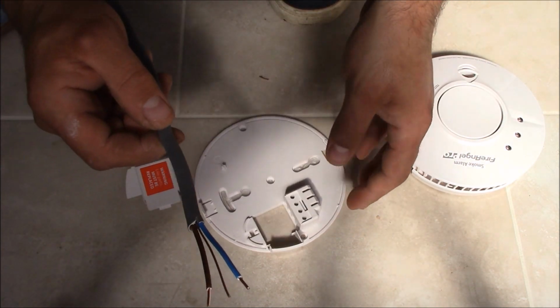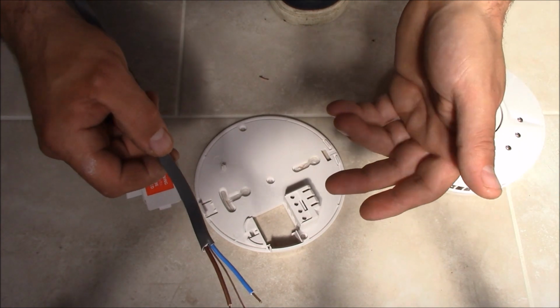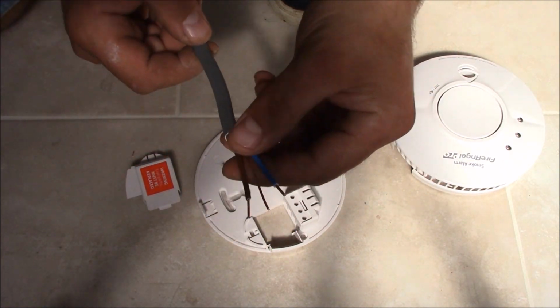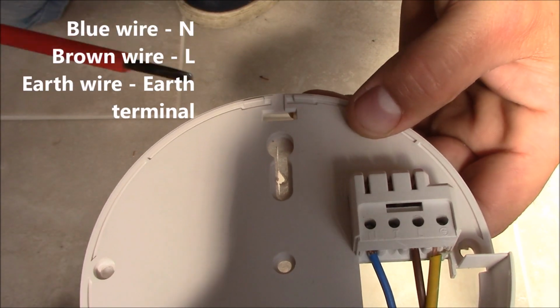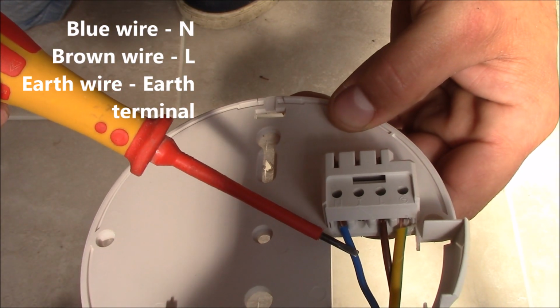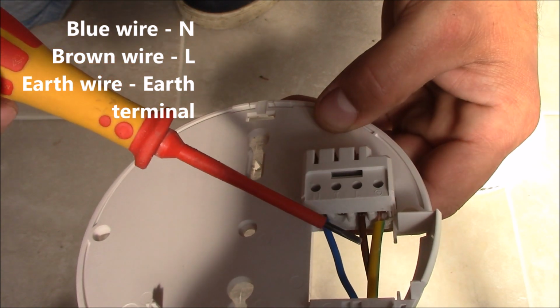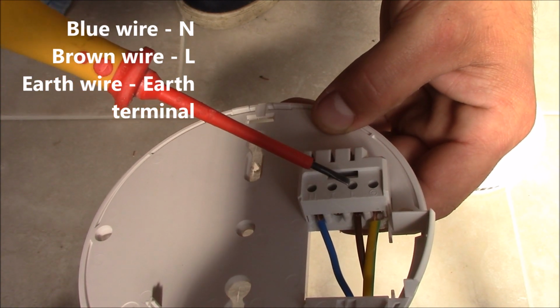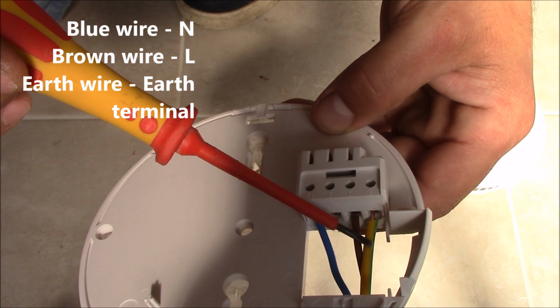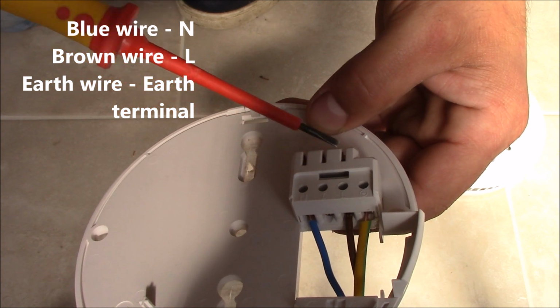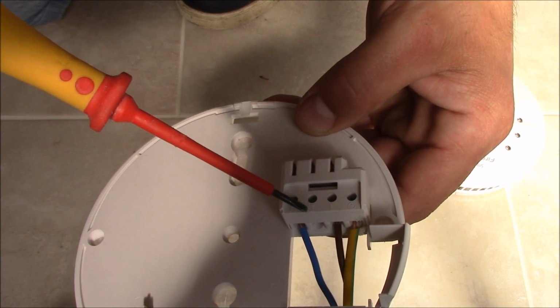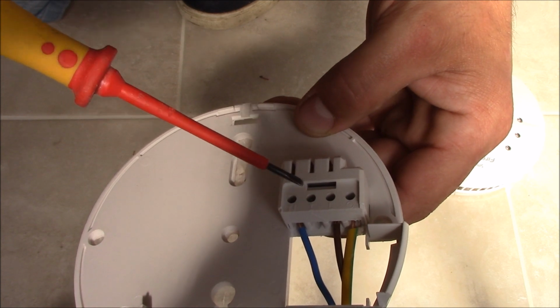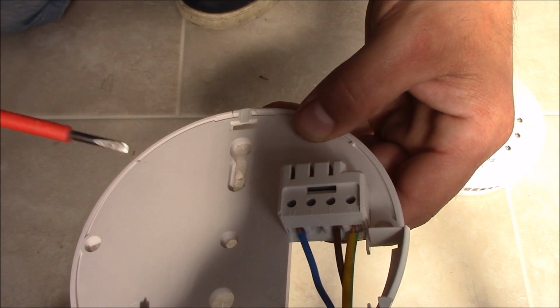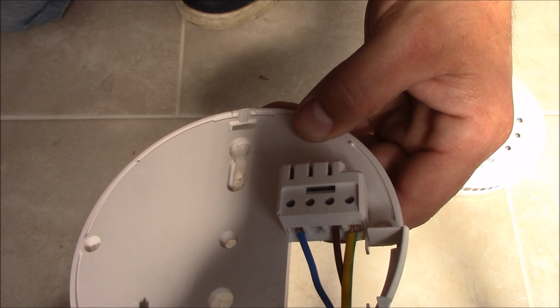So the first one, you have to connect it from the consumer unit to the first smoke alarm, and you use 1mm cable, twin and earth. So that's how it should look. So blue wire neutral to neutral terminal, brown wire live to live terminal, and the earthing wire to earthing terminal here. So this terminal with letter I on it just stays for interconnection with another smoke alarm.